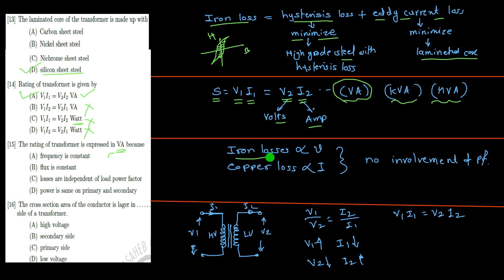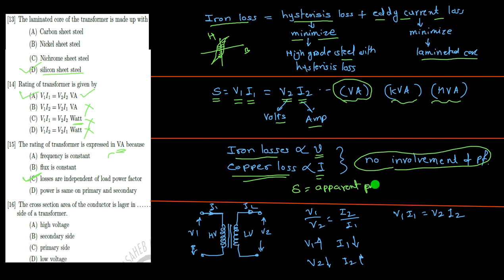Why? Because iron losses in the transformer are constant, proportional to voltage, and copper losses are proportional to current. So they are not depending upon the power factor, there is no involvement of power factor in this case. Hence the losses are independent of the load power factor. Hence the rating of the transformer is measured in terms of VA, or in terms of apparent power. Okay, S is nothing but what?